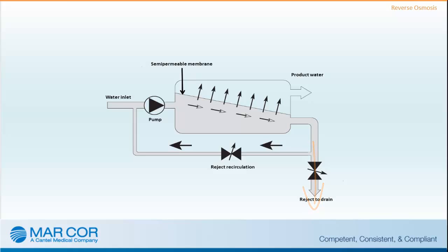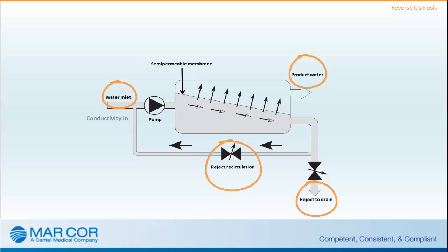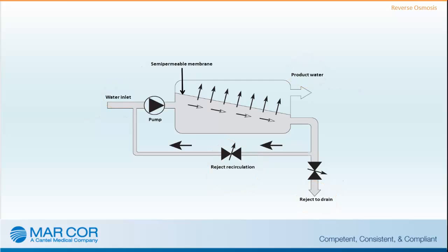The CWP displays feed water flow rates, product water flow rates, RO reject and return flow rates. Conductivity of the feed water and product water are also displayed. Recovery rate and rejected flow rates are displayed in percentages for monitoring the CWP reverse osmosis parameters and process.